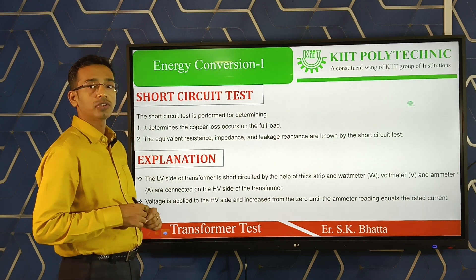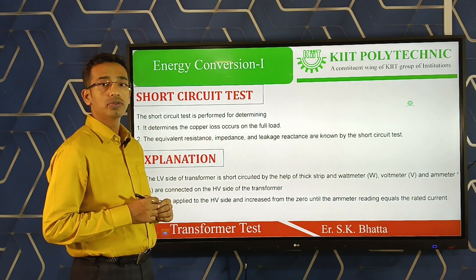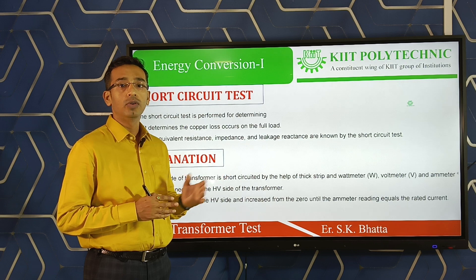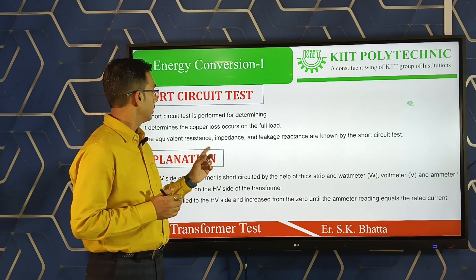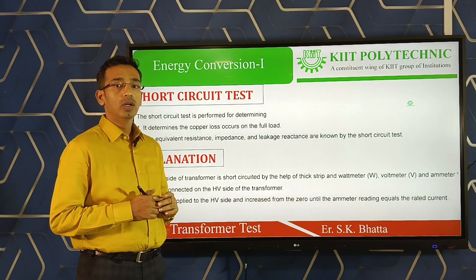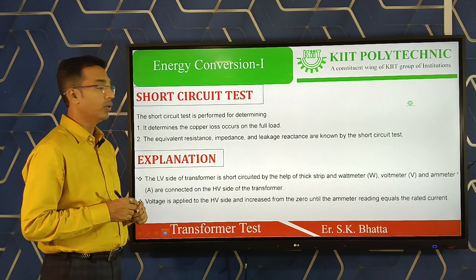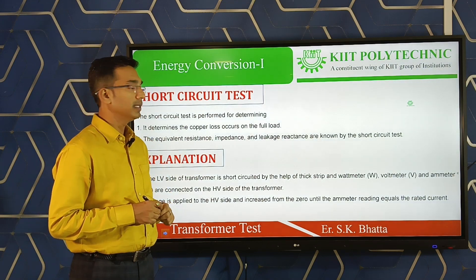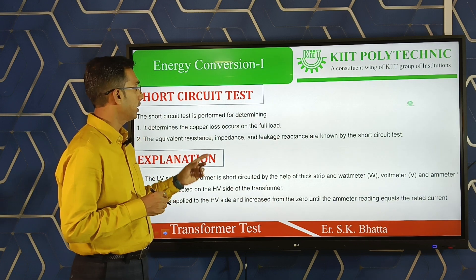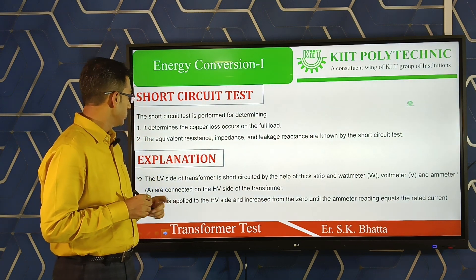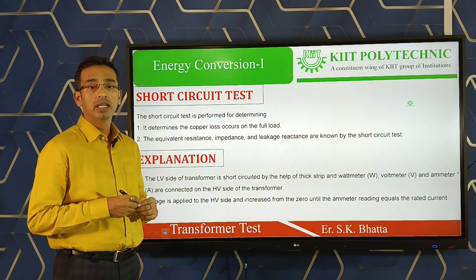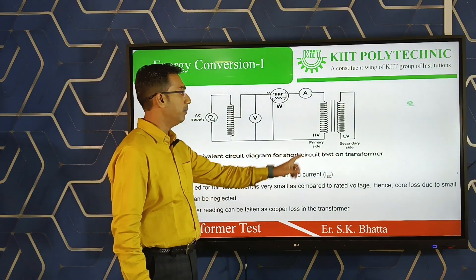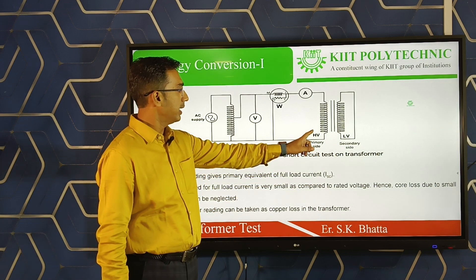Now coming to the short circuit test. The purpose of the short circuit test is to determine the copper loss of the transformer on full load, and also to find the equivalent resistance, impedance, and leakage reactance — the winding parameters. In this test, as the name suggests, the secondary side (LV side) of the transformer is short-circuited through a thick wire.